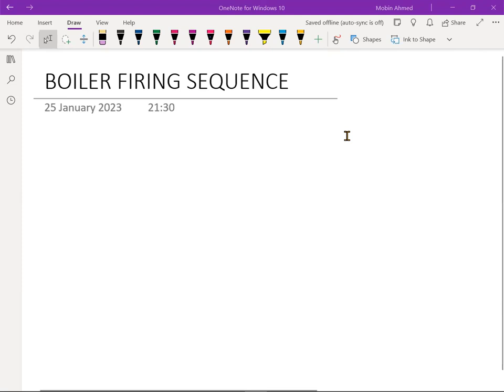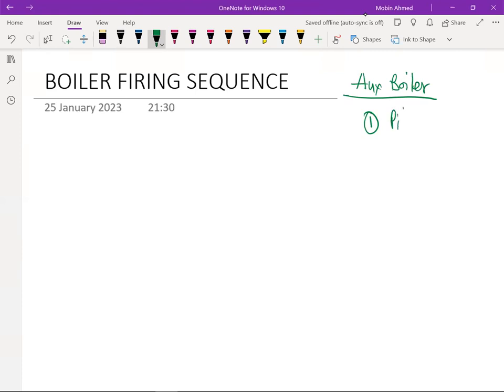So now we are seeing a boiler, which is going to have an auxiliary boiler. Okay, I am going to tell you the auxiliary boiler firing sequence. This auxiliary boiler has both the pilot burner and the main burner. I will tell you the difference if only the main burner is there and the pilot burner is not there, but the sequence remains almost the same, so there are no changes. If you understand this sequence, you will understand it for the main burner only.